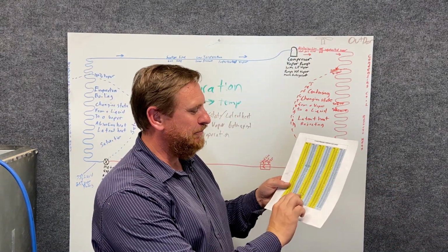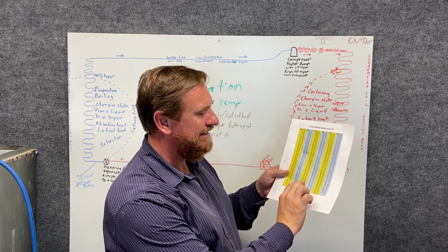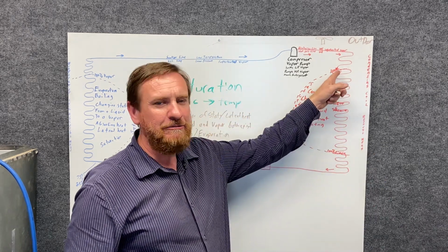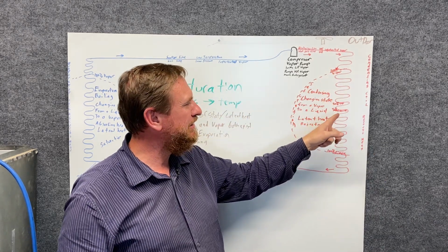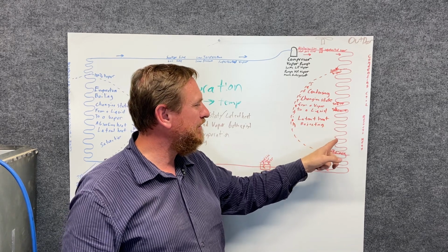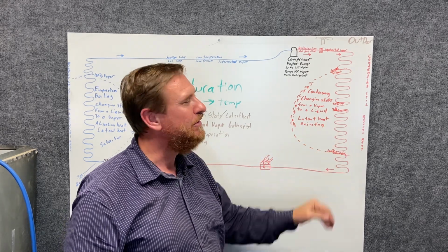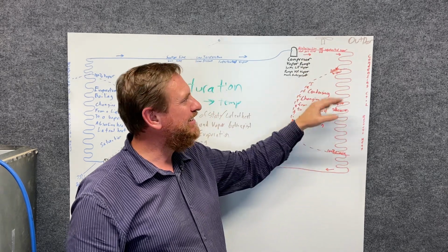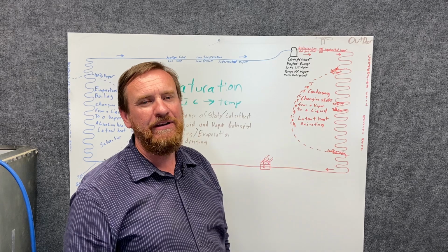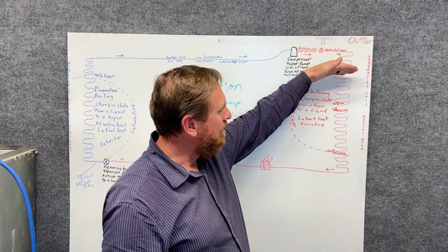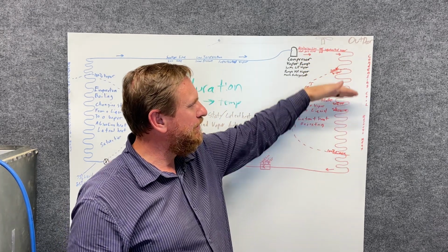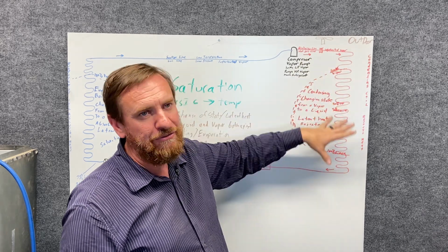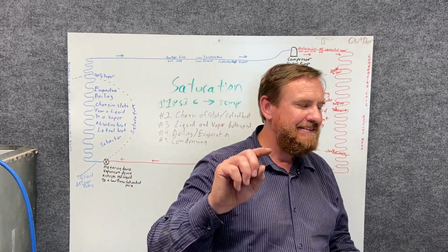My refrigerant over here is boiling, or condensing at 96.2. So here it's 96.2 all the way across. It's going to be the exact same temperature throughout saturation until all of the liquid and vapor is either gone. Here, all of my vapor turns into a liquid or all of my liquid turns back to vapor. As long as there's both together, it's going to be at saturation.